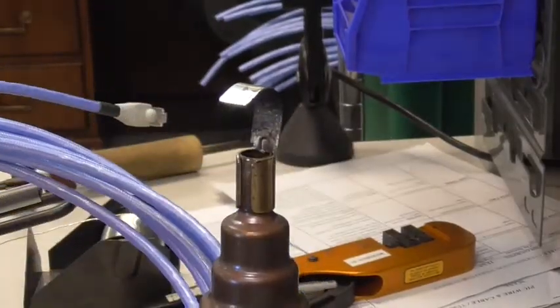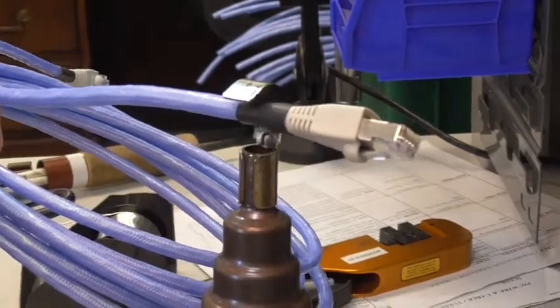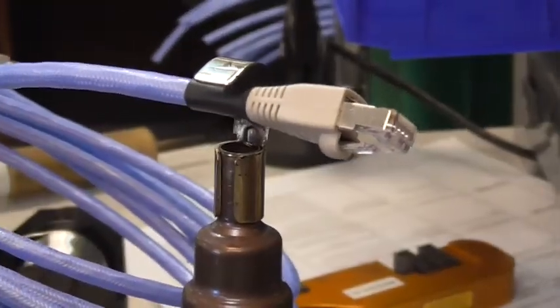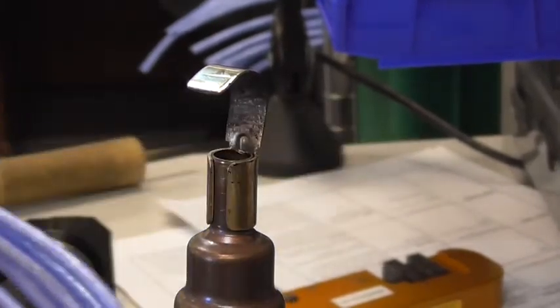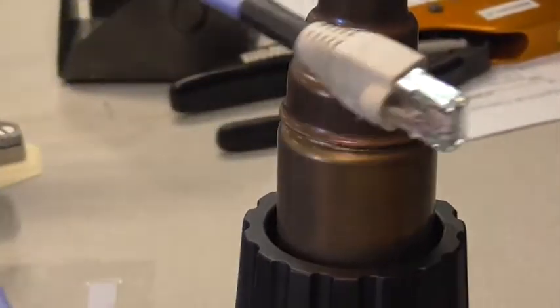Slide up the 0.75 inch piece of heat shrink to the back end of the boot and use a heat gun to shrink it, ensuring the heat is kept away from the boot or it will deform and melt. This concludes our termination instructions.